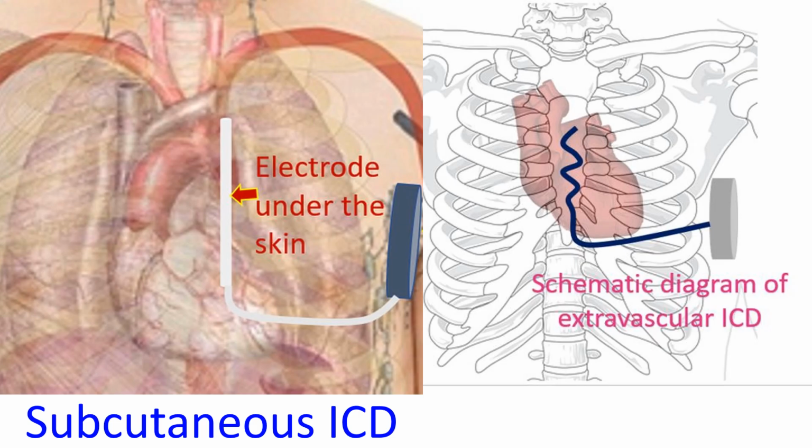The most commonly implanted ICD is also called transvenous ICD because the leads are introduced through the veins into the heart. A purely subcutaneous ICD with lead implanted subcutaneously is also available. Recently, an extravascular ICD has been tested with a substernal lead with performance better than purely subcutaneous ICD and almost nearing the transvenous ICD.